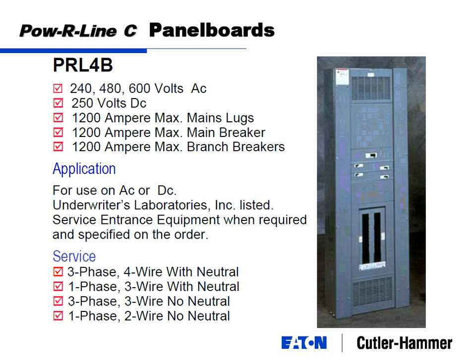So the 1s and the 2s and the 3s are all about 6 inches deep. Powerline 4s are about 11.5 inches deep. The minimum height of a Powerline 4 is 57 inches, and it goes up to 90 inches high. It gives you all the way up to 1200 amps capability for main breaker, main lug, and the key here is also the branch breakers. So I can put a 1200 amp main breaker and 2 1200 amp branch breakers if I want in the panel board design.